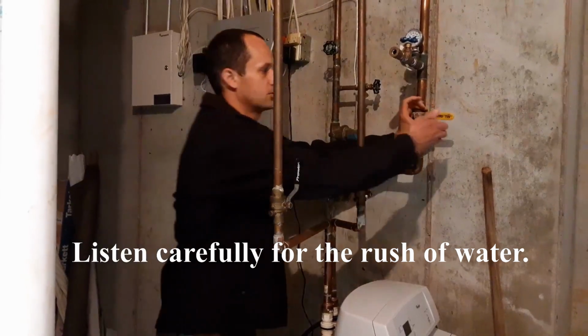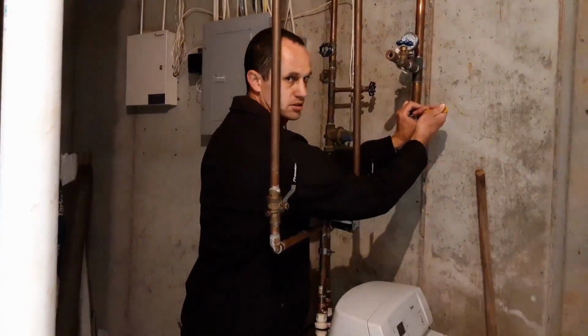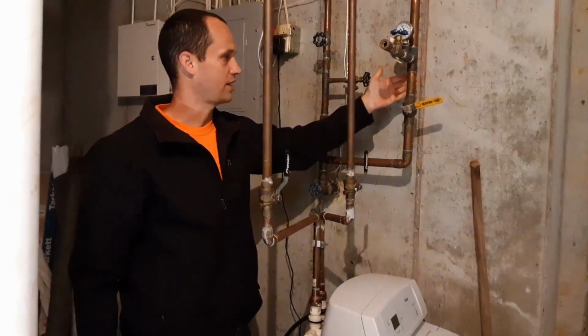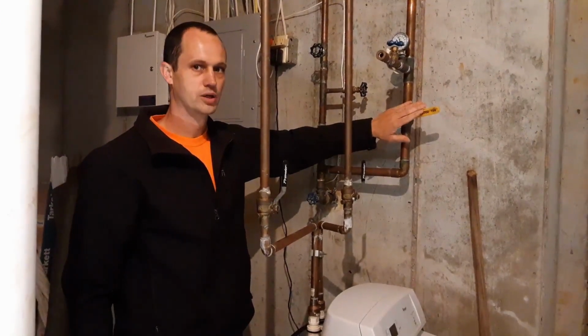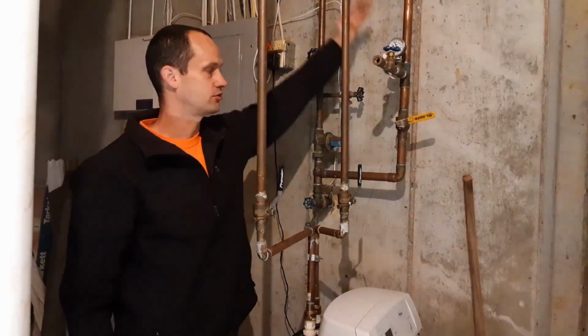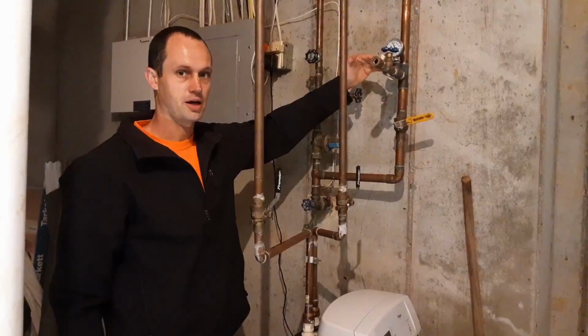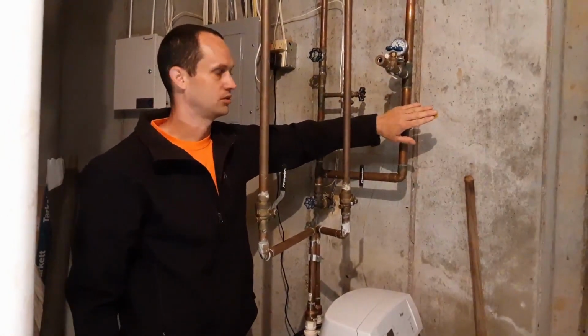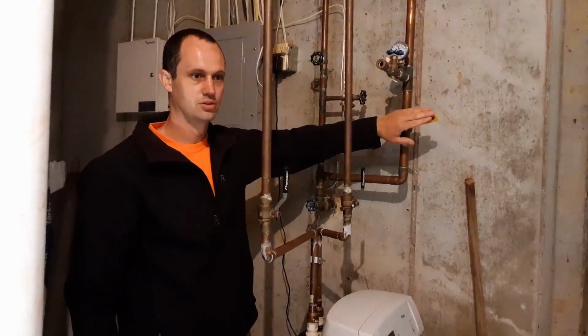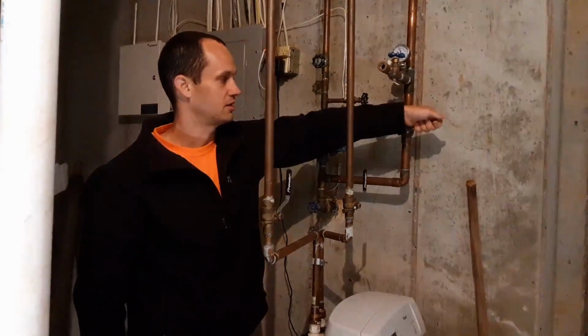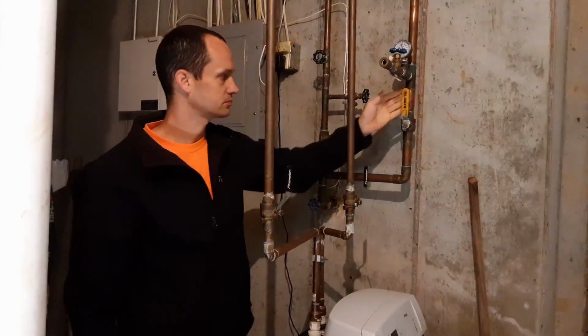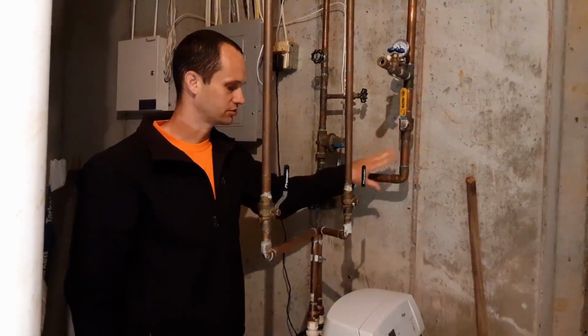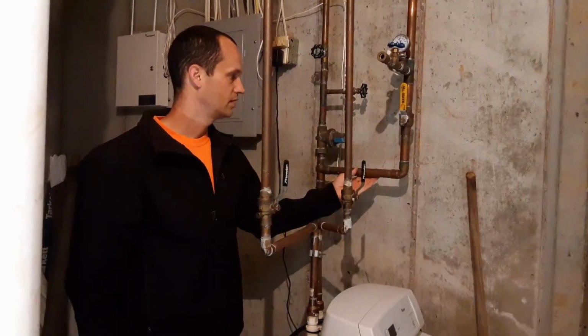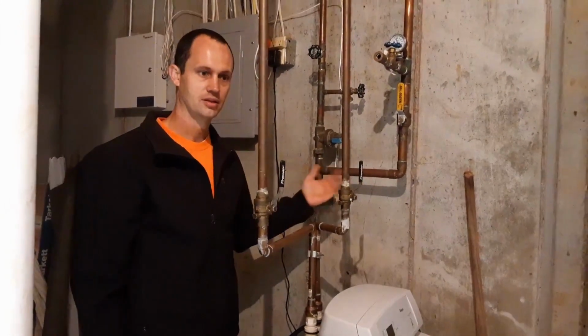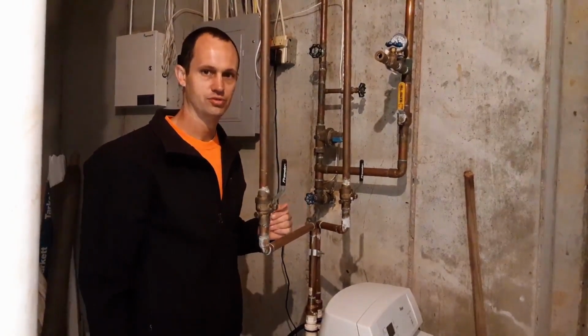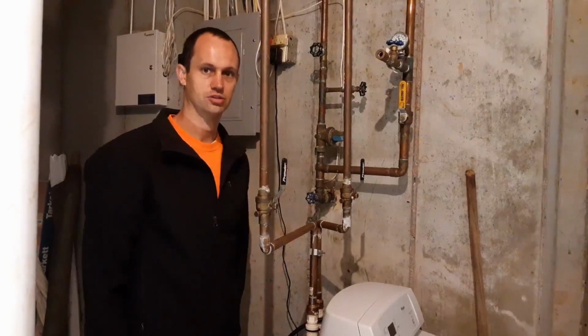So I'm going to open this valve, and I'm going to just crack it open first. Just open it just a little bit. Basically, there's a large amount of air in this pipe, and if you open this valve too quickly, that slug of water is going to travel and compress that air, and it can burst the pipe if it goes too quickly. So I'm going to turn this open just a little bit at first until I hear the sound of water rushing through the pipe stop, and then I can know that I can open it the rest of the way. Now after you open this, just check that there's no leaks, that there's no water dripping from anywhere, and make sure that everything is good to go. And then we're going to go back outside and open the 2 valves on the backflow prevention device to pressurize the rest of the sprinkler system.